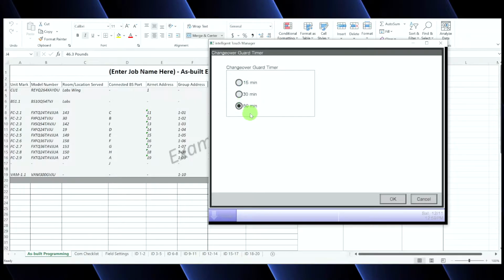And it is very, very possible to screw this up. If you're changing over every 15 minutes, plus you're using a single set point with a tight changeover deadband, you're going to have performance problems. You're going to have comfort problems. So make sure that you pick the time it takes to change over properly. I'm going to go ahead and pick 30 minutes just for this example. That does not mean you need to pick 30 minutes. Again, use the proper amount of time that is going to be needed based on how you're setting up your set points, single or dual set point, and your changeover deadband.